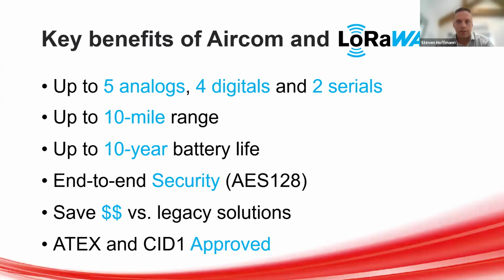Key benefits of AirCom, which leverages LoRaWAN as the communication protocol. You can bring into a single AirCom unit up to 5 analogs, 4 digital, and 2 serial inputs from any instrument. You can send that data up to 10 miles, depending on topography, and have up to 10-year battery life in that application to power the sensor and take the readings. The data is encrypted end-to-end, AES-128 encrypted. And it allows you to save money compared to legacy solutions. Typically, installing our system costs less than just bringing out, say, a hydrovac machine to trench and run conduit. And it is ATEX Zone 0 and Class 1 Div 1 approved, so it can sit right there in the hazardous areas, taking readings from sensors and sending those back.